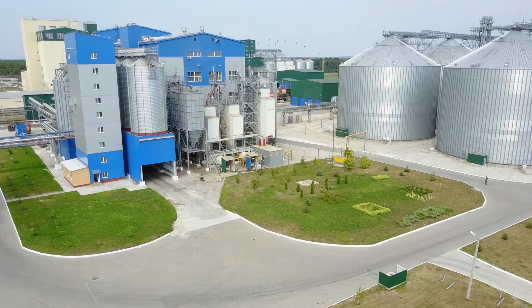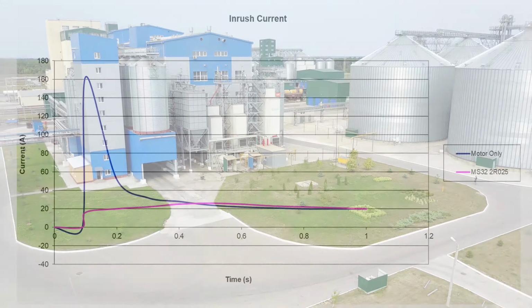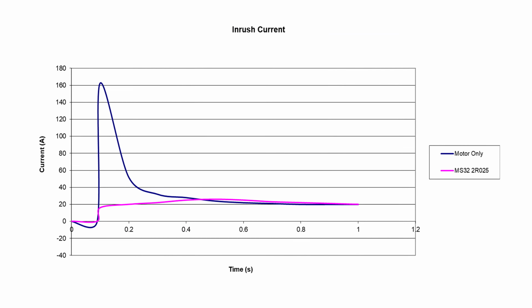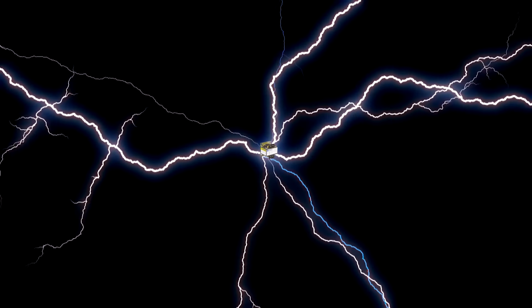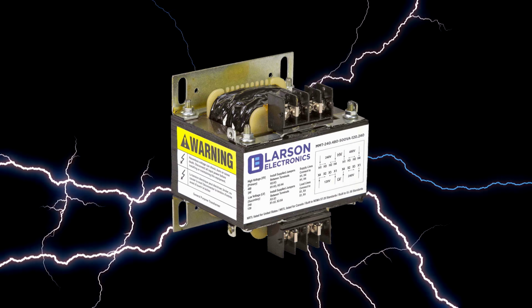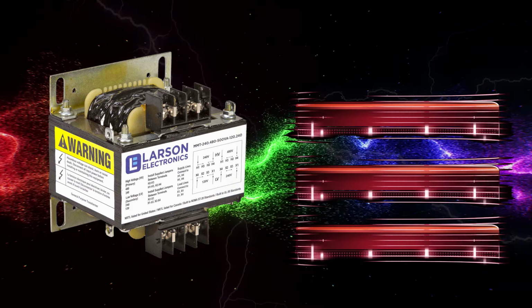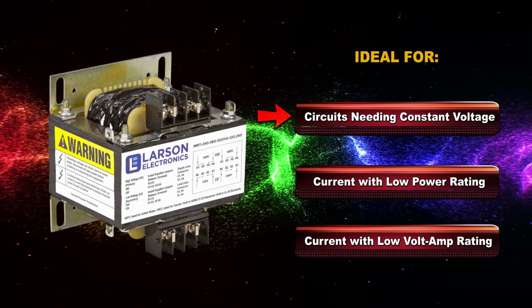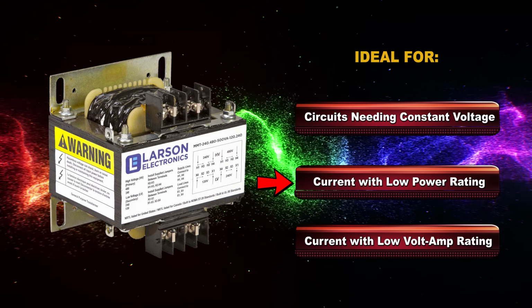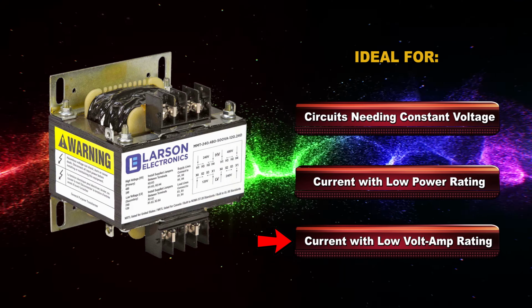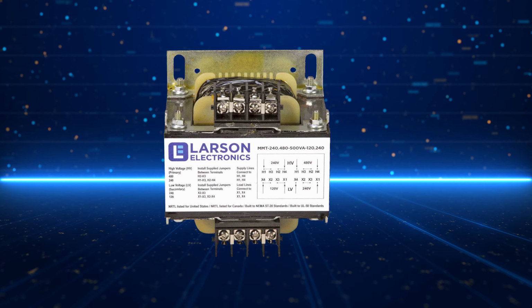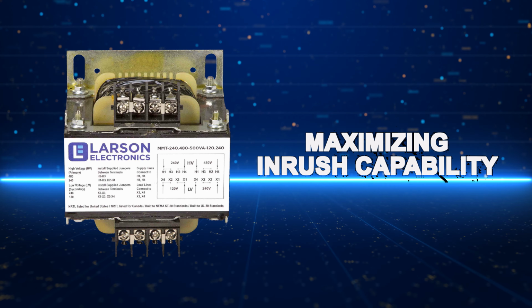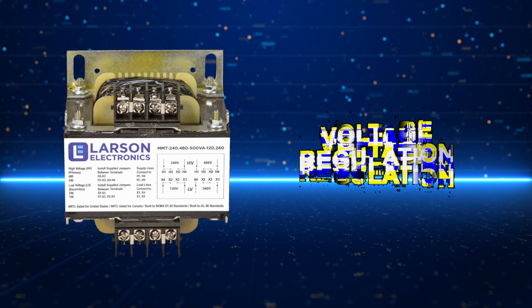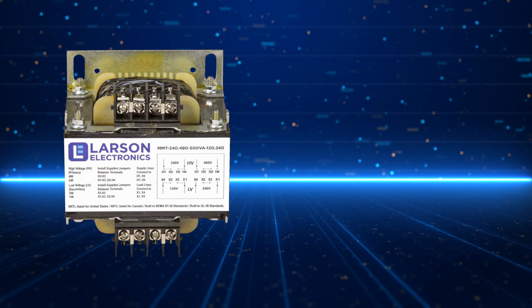For facilities requiring secondary voltage stability when experiencing overload conditions such as inrush currents, a control transformer is essential. Control transformers are ideal solutions for circuits needing constant voltage or current with lower power, voltage, and amp ratings. They are capable of maximizing inrush capability as well as voltage regulation on the output side at startup.